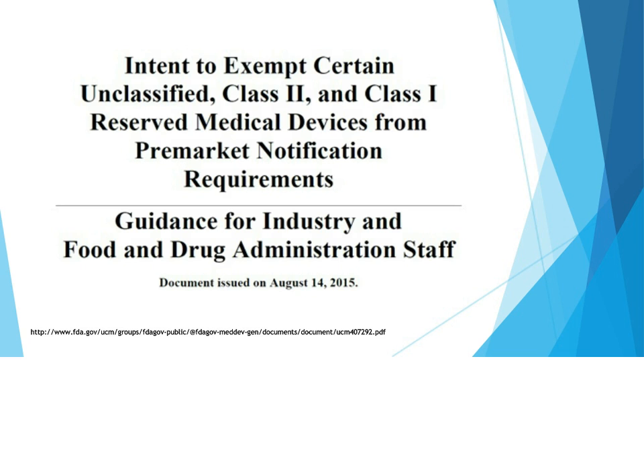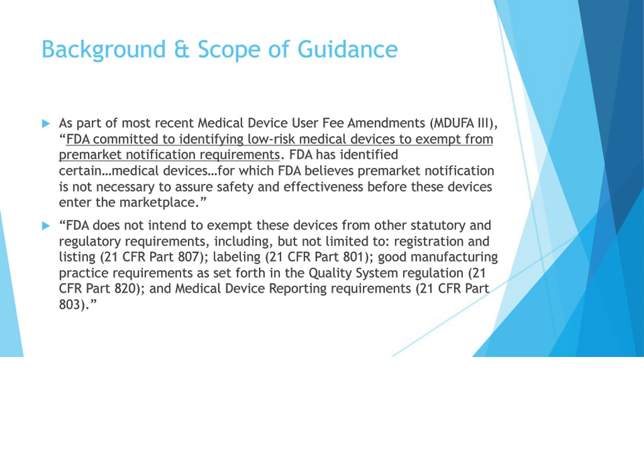During MDUFA 3 negotiations that I mentioned earlier, FDA also committed to identifying low-risk medical devices to exempt from the 510K pre-market notification requirements. FDA has identified specific unclassified medical devices, Class 1 reserved medical devices, and Class 2 medical devices, for which FDA believes pre-market notification is not necessary to assure safety and effectiveness. However, the scope of the guidance makes it very clear that it does not intend to exempt the devices listed in the document from other requirements such as registration and listing, labeling, good manufacturing practices, and medical device reporting requirements. These are often referred to as general controls.